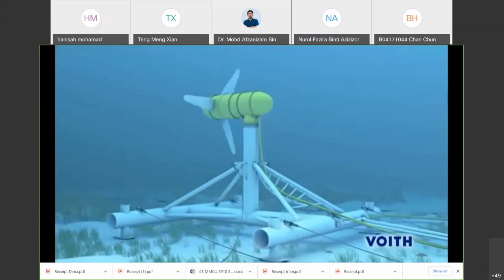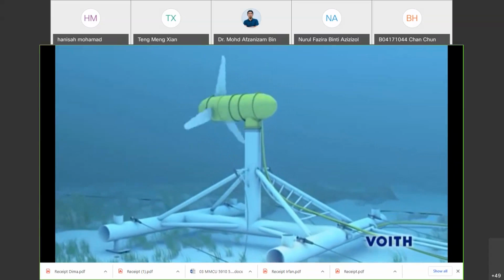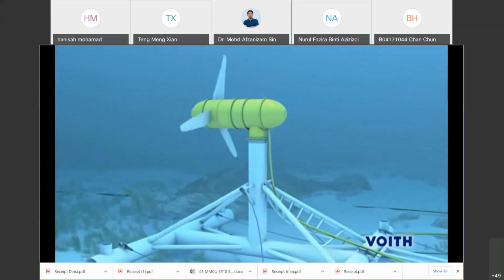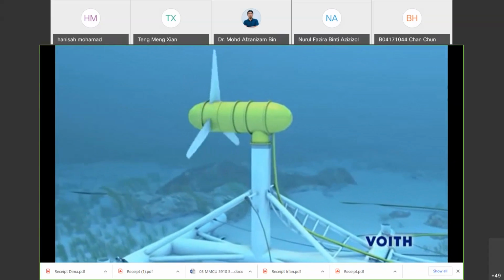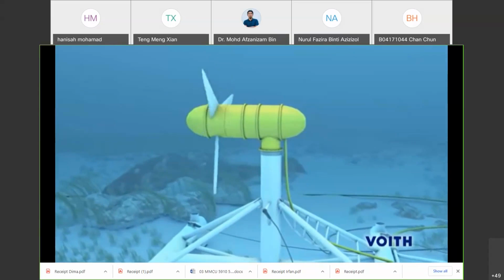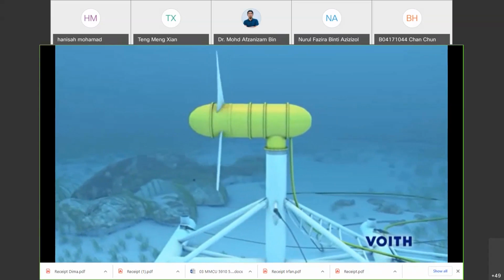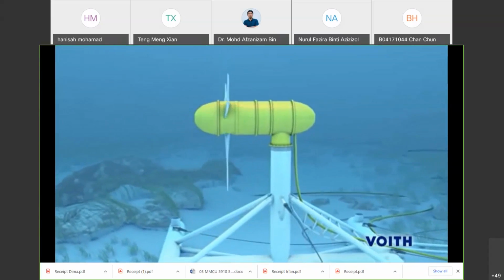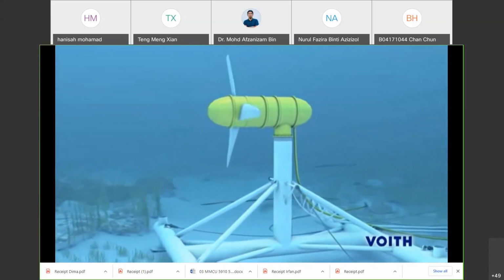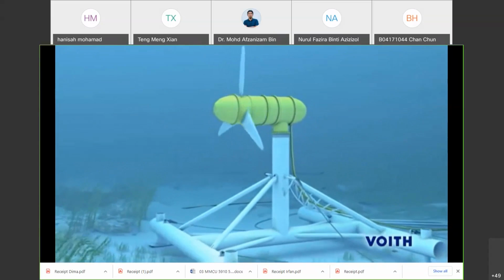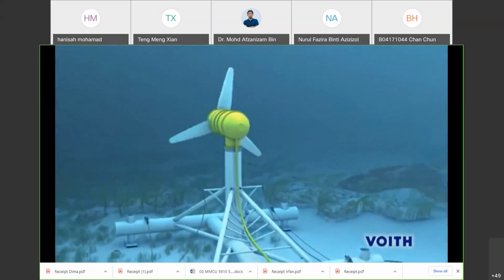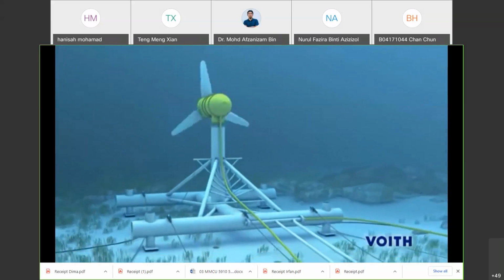During the development of the turbine, special attention was paid to simplicity, robustness, and eco-friendliness. The design has eliminated failure-prone transmissions and operates without oils and grease. Seawater is used for bearing lubrication. Another special feature lies in the avoidance of complex and sensitive seals. This has been achieved by designing the generator components to operate immersed in seawater.